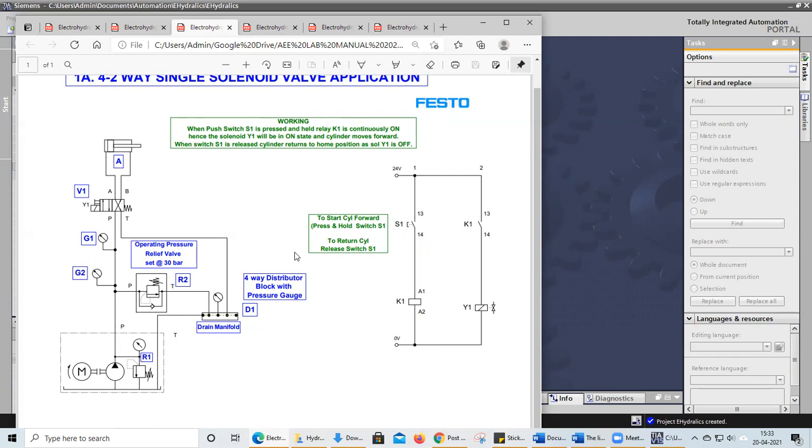For example, this solenoid may be running with very high voltages, assume some 230 volts or 420 volts or 11 kilovolts. So we cannot go and turn on this directly. So we will energize one more coil. This coil will create a magnetic field.